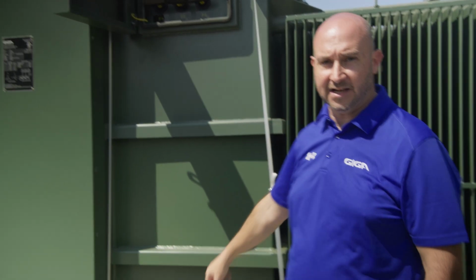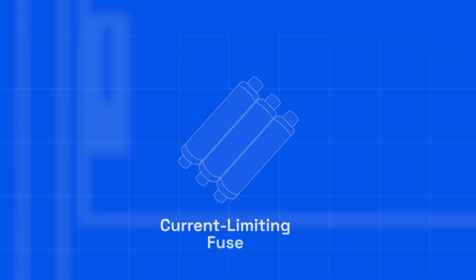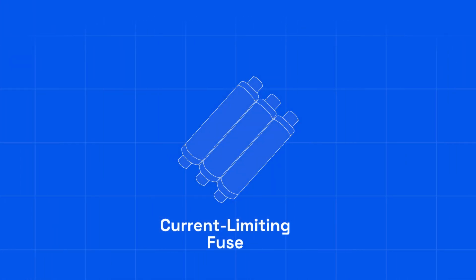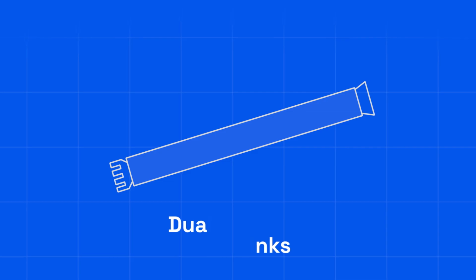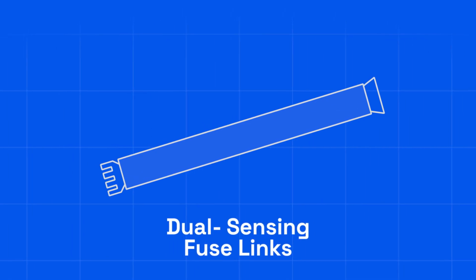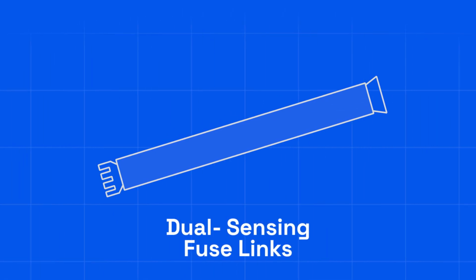Current limiting fuses mounted here inside the transformer tank provide protection for your downstream equipment against high energy faults. At Giga, we build pad mounts with both bayonet and current limiting fuses. That way you get a full range of protection. With these dual sensing fuse links, your protection can be more precise because you detect both heat and current.